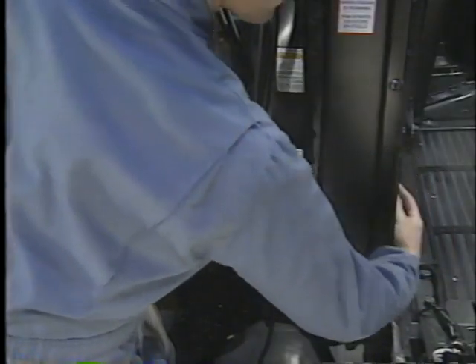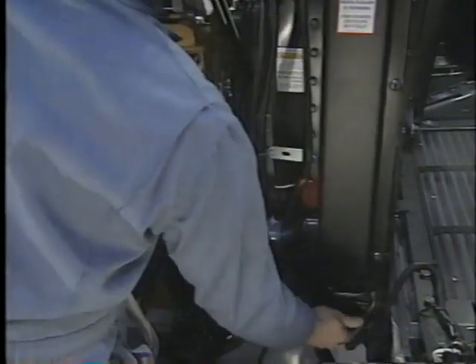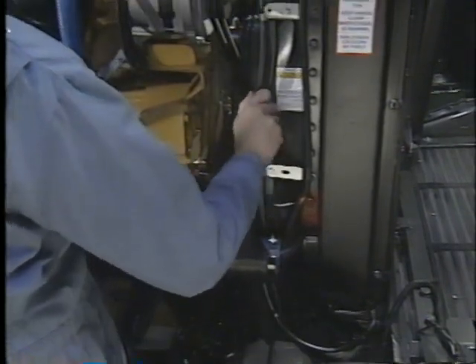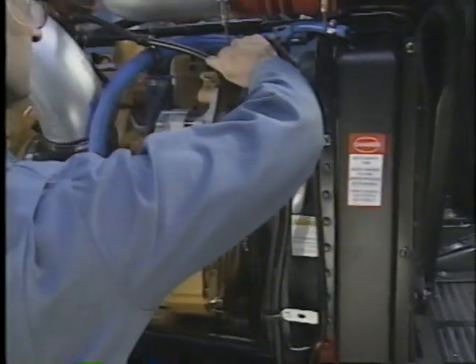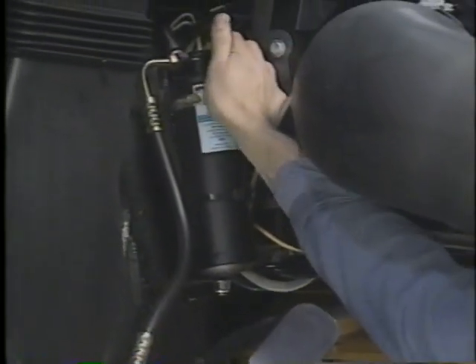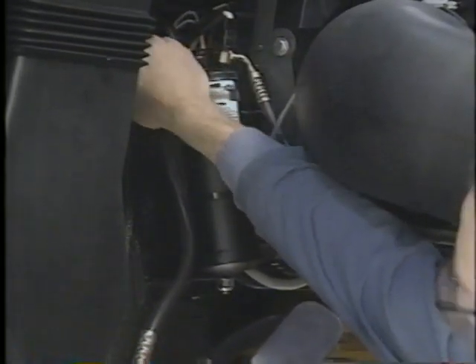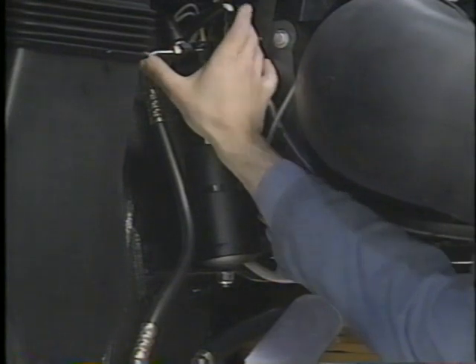The line from the condenser to the receiver dryer should feel warm. A cool spot indicates a restriction. If the line is hot, the condenser isn't working correctly. The inlet and outlet of the receiver dryer should be the same temperature. If not, the filter could be plugged.